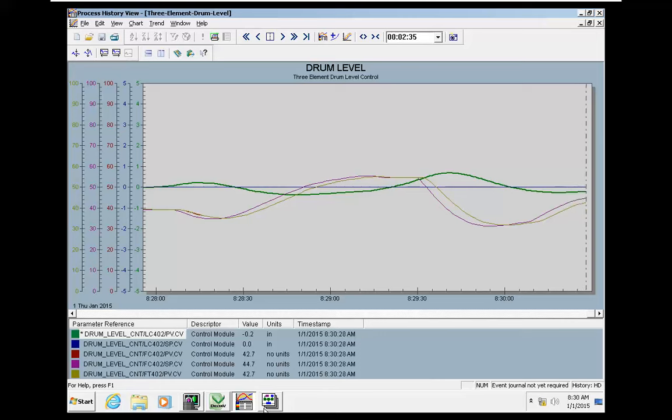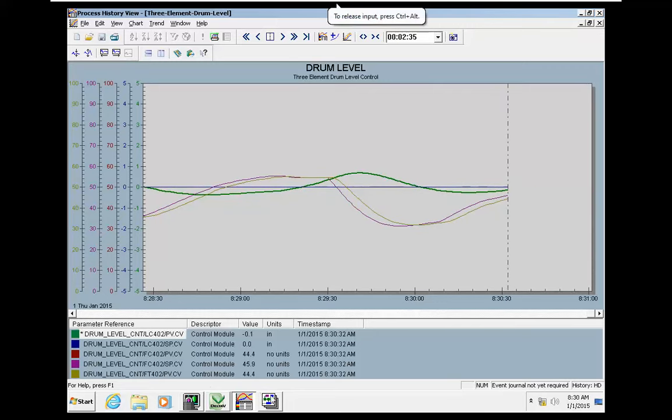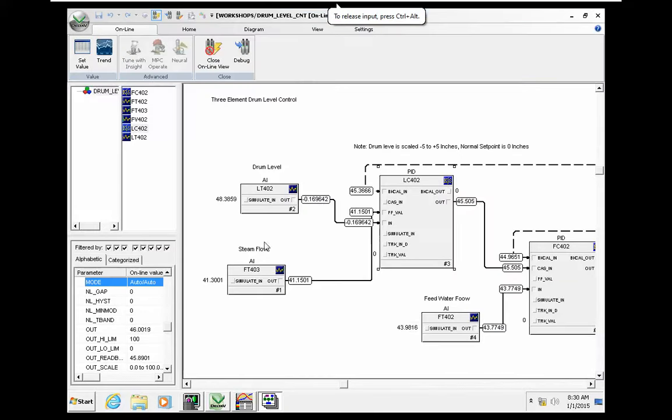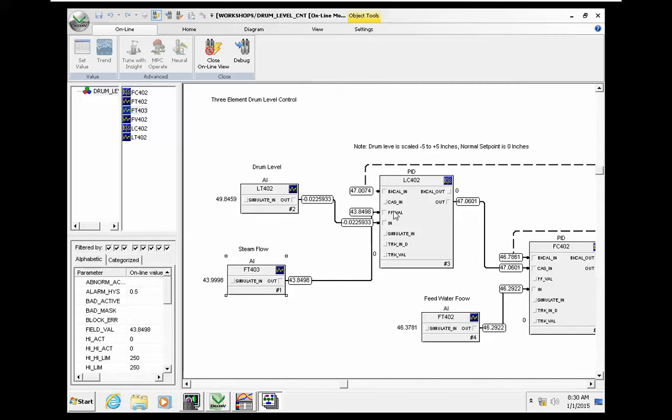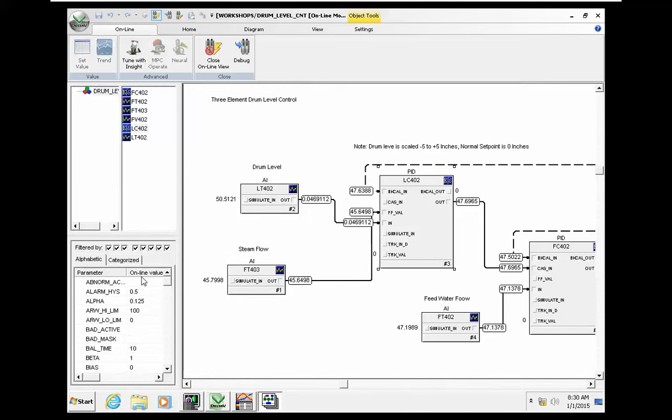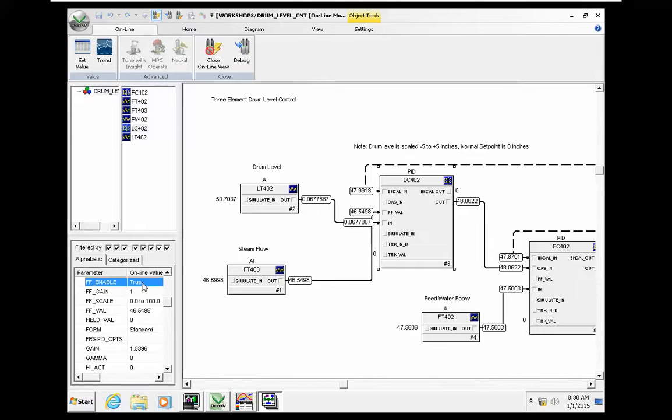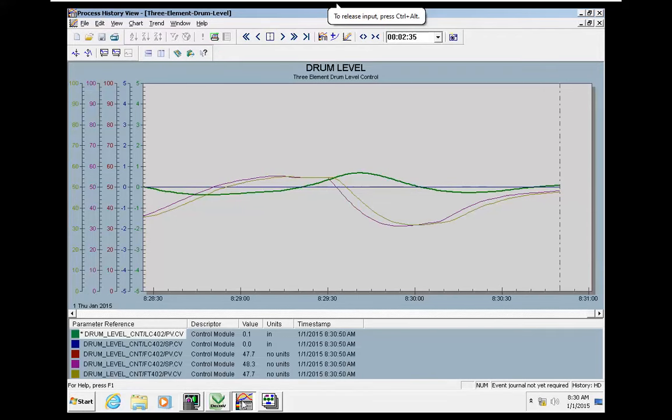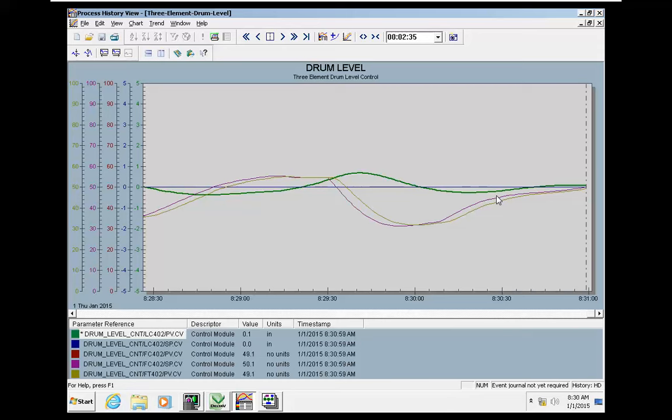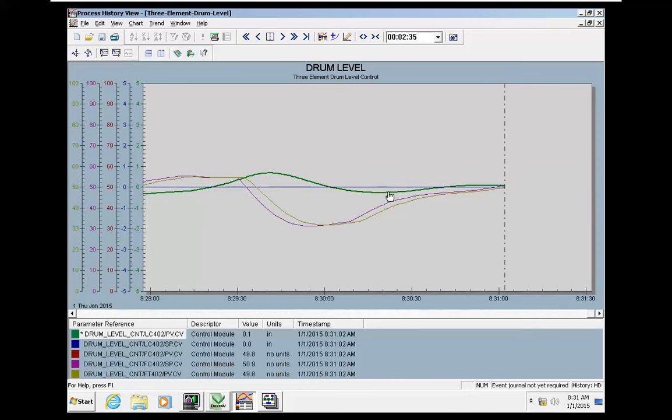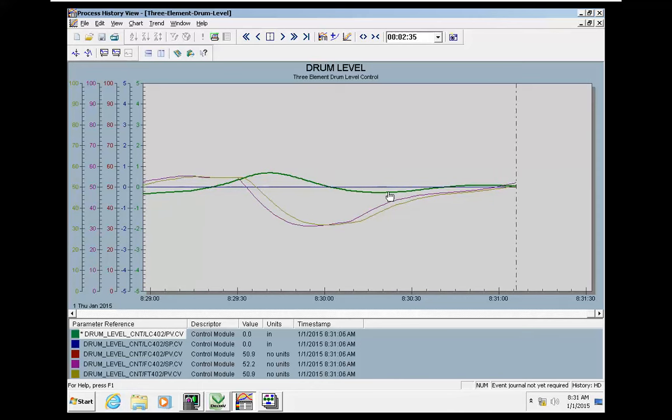To get the best reactions, you can see that steam flow is fed to the feedforward value and by enabling the feedforward in PID1, we are making it steady. You can see that the level control is getting less variations. It's a great tool.